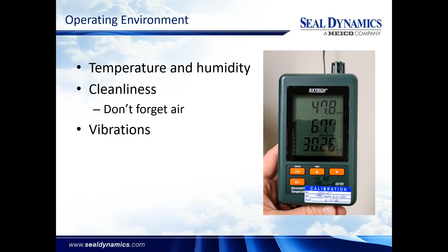Vibrations are a big deal. I've worked in a shop where we had very large mills, and we had a CMM right out on the shop floor. Before those mills went in, a large part of the concrete was dug up and relaid with a barrier of a dampening material to prevent those machines from affecting each other, as well as the CMM around them. So it's important to understand that an extremely sensitive CMM can be subject to those vibrations, get false triggers and things of that nature.